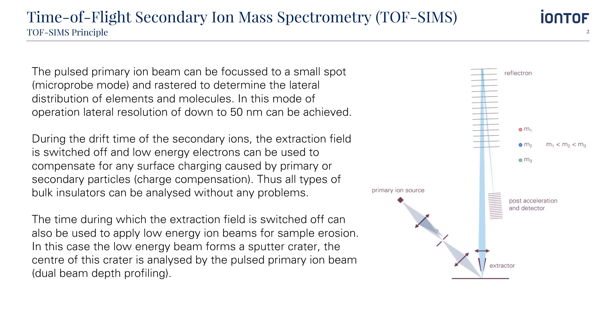During the drift time of the secondary ions, the extraction field is switched off and low-energy electrons can be used to compensate for any surface charging caused by primary or secondary particles. Thus all types of bulk insulators can be analyzed without any problems.